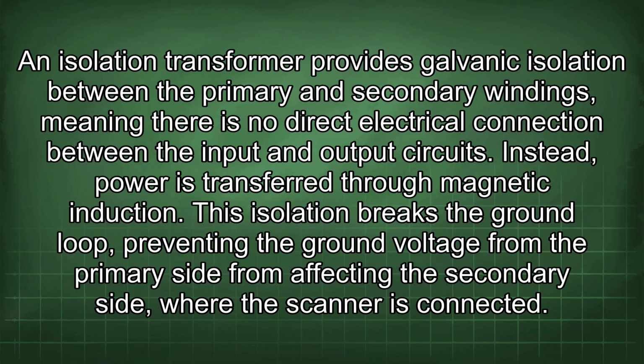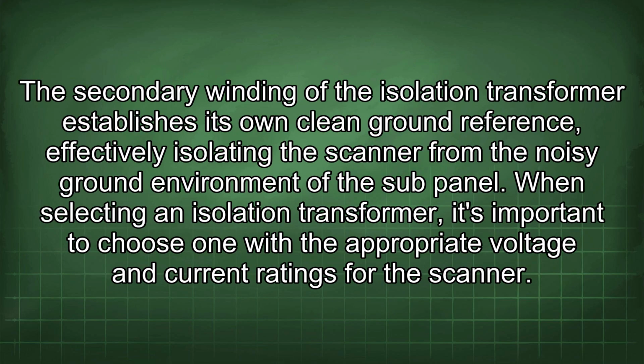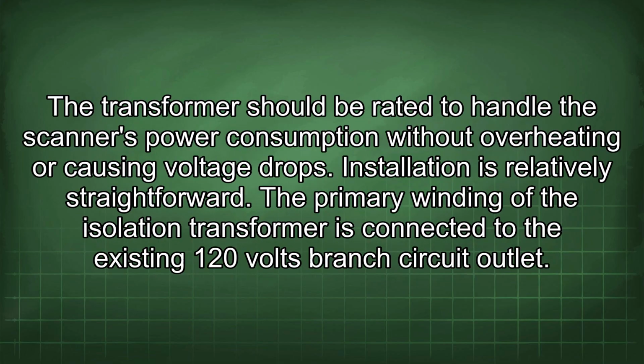This isolation breaks the ground loop, preventing the ground voltage from the primary side from affecting the secondary side, where the scanner is connected. The secondary winding of the isolation transformer establishes its own clean ground reference, effectively isolating the scanner from the noisy ground environment of the subpanel. When selecting an isolation transformer, it's important to choose one with the appropriate voltage and current ratings for the scanner. The transformer should be rated to handle the scanner's power consumption without overheating or causing voltage drops.